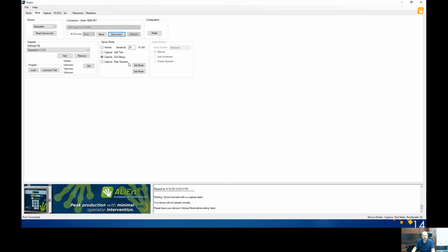And we can see this sensor is already in the full debug. If we put it in switch position 0 and set it between normal and full debug, we can change the mode. So you can see normal is the normal operation mode. When you're done working with a sensor, you always want to go back to normal. We can do a self-test. We can do full debug, which shows us the baseline and switch setting, all the detail I showed you in some of those other screen captures. Or if you want to see the raw data with no filtering, you can see these raw samples. And then you can click set or get mode. But we're already in the full debug mode.